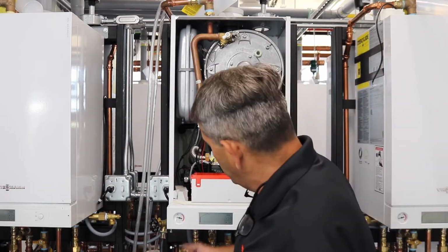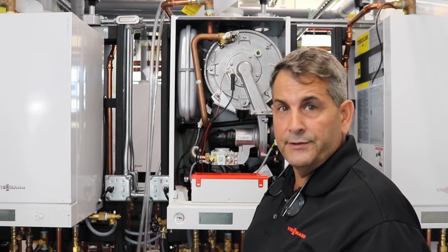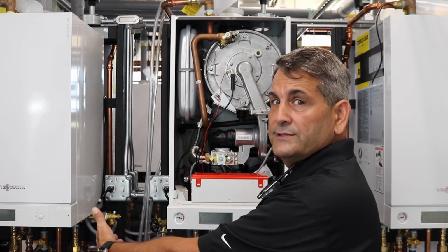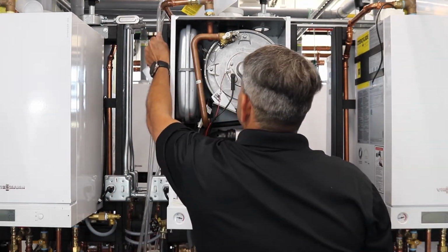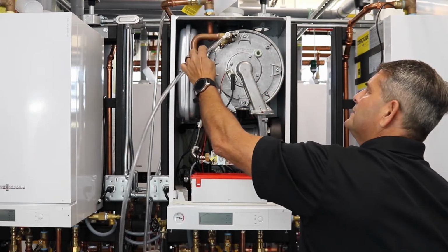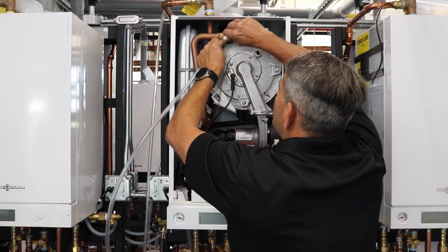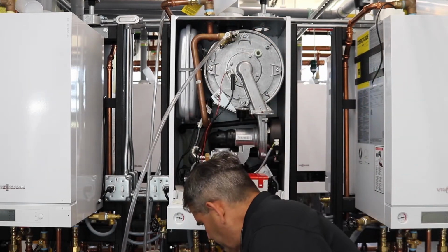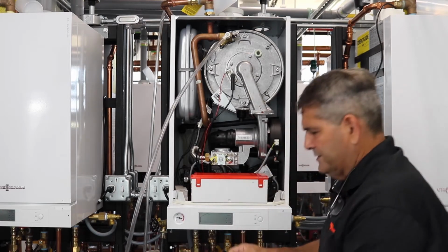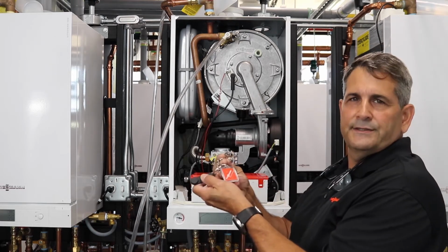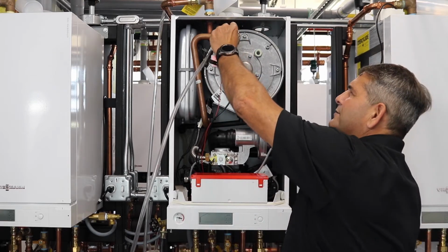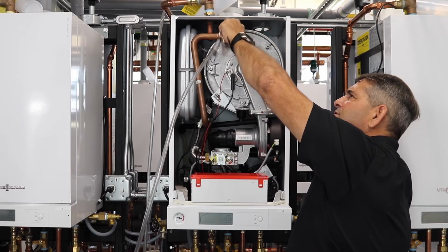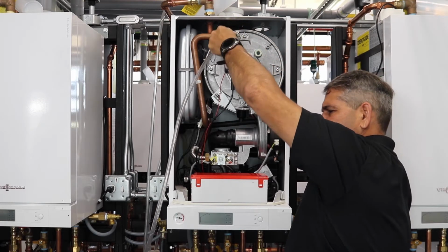I did set up a hose prior to the class. So we have a hose on our drain line on the left-hand side of the boiler itself. I also have our hose for bleeding. We want to make sure we check for air. This does come with the boiler itself, as well as a key that comes with it. You'll find this key with your installation kit. So first we're going to check to make sure that there's no air in the system. I open the bleeder. As you can see, we do have water in the system.